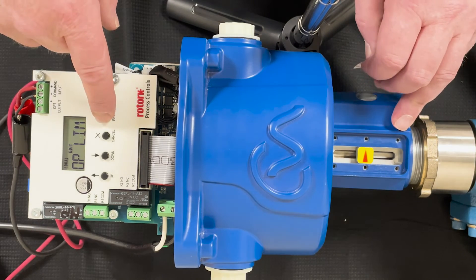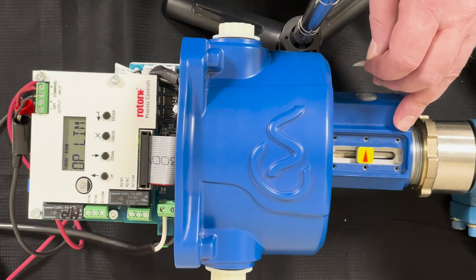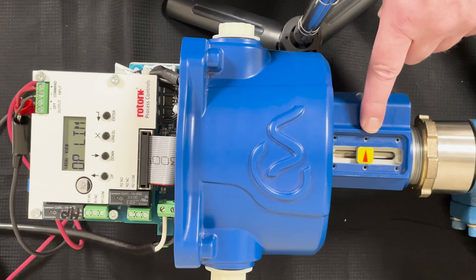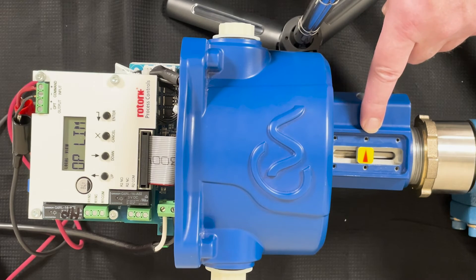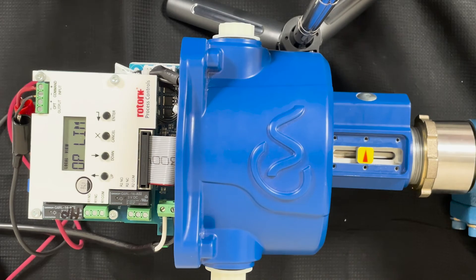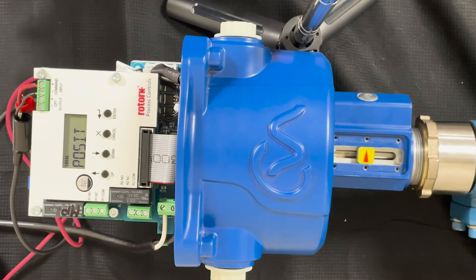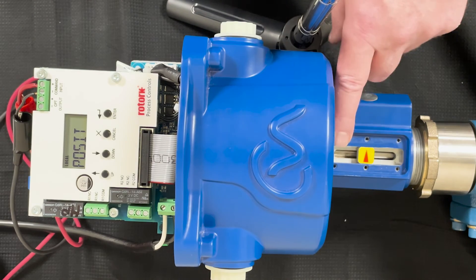Once we saved it, now your 4 and 20 are set, with 4 being zero and 20 being 100 percent of flow. Now to check your 4 to 20 signal and your span on zero and 100, we must put this back into remote.